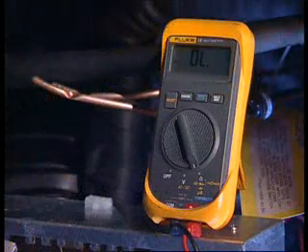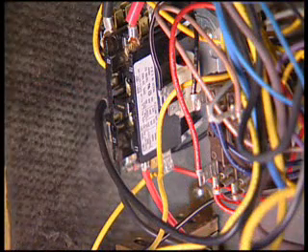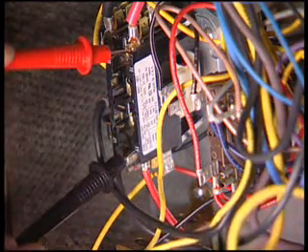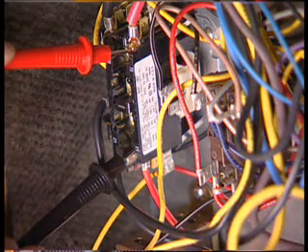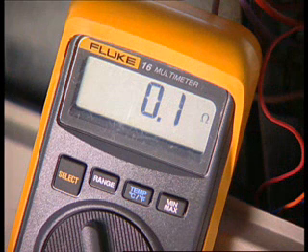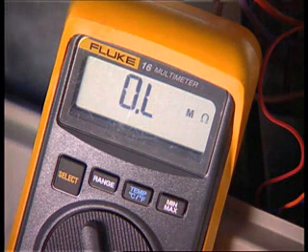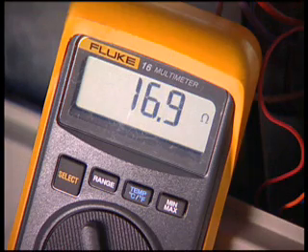If an ohm meter is used to check the contacts, there should be no current flowing through the contacts, and the coil should be de-energized. The wires should also be disconnected from the contactor contacts. When the contacts are in the closed position, the resistance reading through the set of contacts should be very close to 0 ohms. Always be sure to check all sets of contacts. A high resistance reading indicates that the contacts are no good.